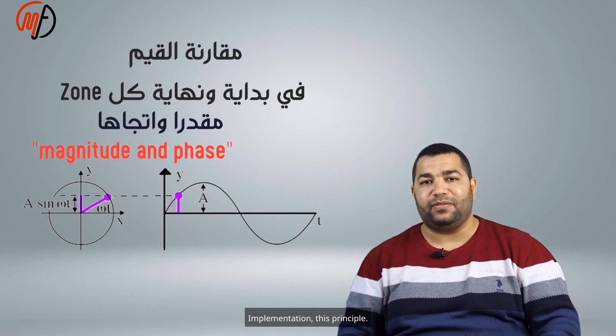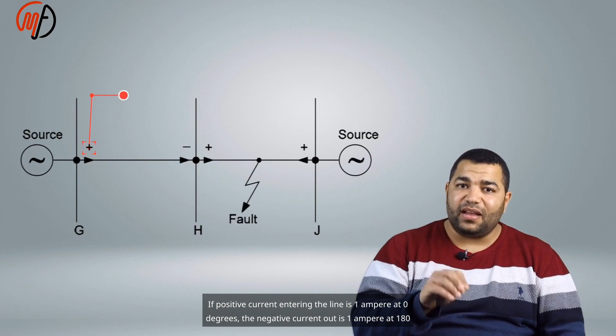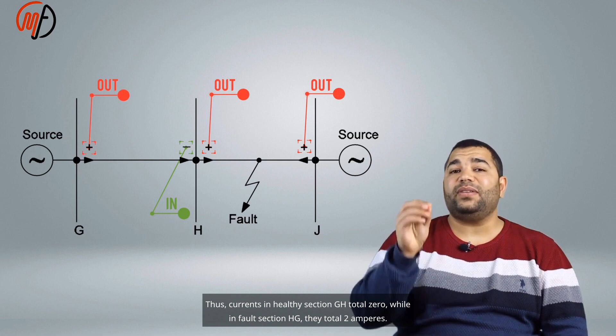Currents feeding the fault area in line HJ are positive as they flow out of the bus bar into the faulty feeder. If positive current entering the line is 1 ampere at 0 degrees, the negative current out is 1 ampere at 180 degrees. Resultant currents are 1 minus 1, or 1 at 0 plus 1 at 180 degrees, totaling 0. Current entering the protected zone is positive, out is negative. Thus, currents in healthy section GH total 0, while in fault section HJ, they total 2 amperes.